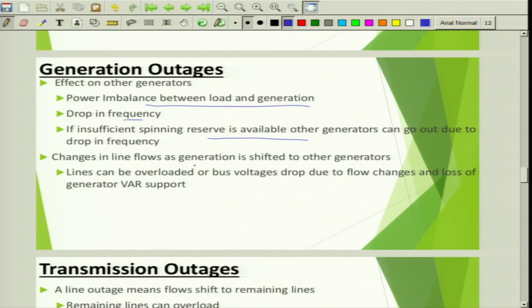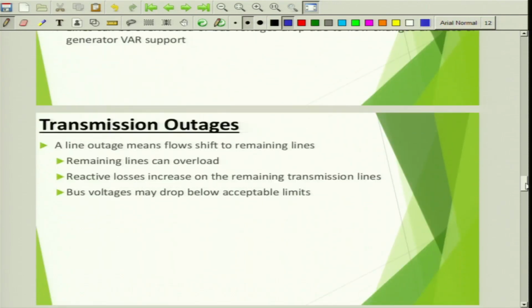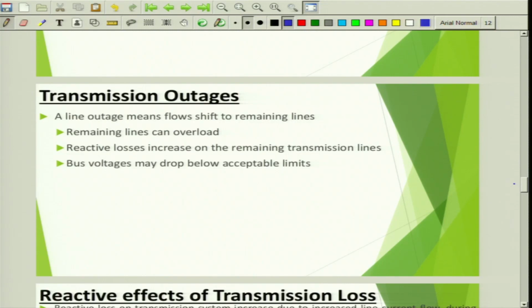So changes in line flows as generation is shifted to other generators. So lines can be overloaded or bus voltages drop due to flow changes and loss of generator voltage support. So if there is damage in one line or increase in line flow at one specific line, then they may get overloaded and voltage drop can happen. I'll go through some case studies also. And with a line outage, flow shifts to the remaining lines. Remaining lines can overload. Reactive losses increase on the remaining transmission lines, right? Because I square R loss increases in that line, and then bus voltages may drop below acceptable limits also because of voltage drop.